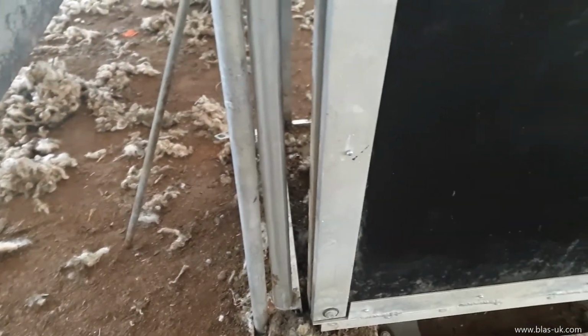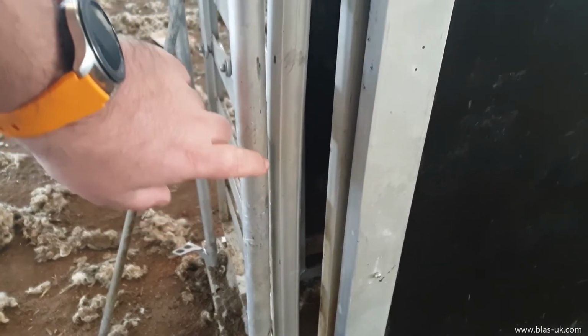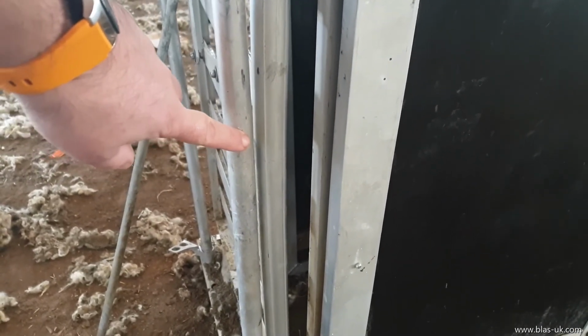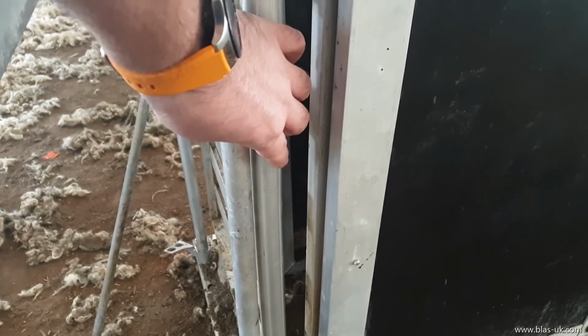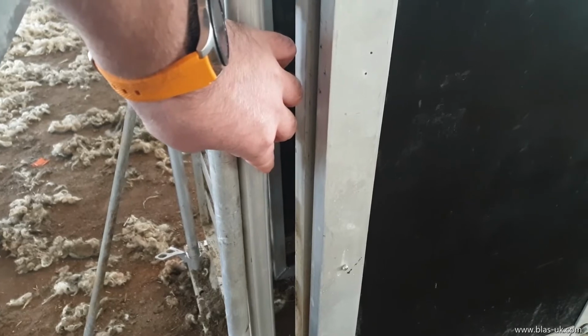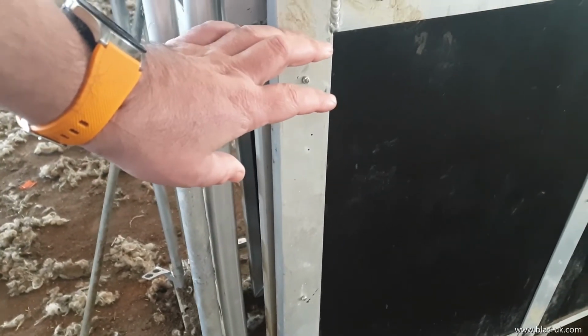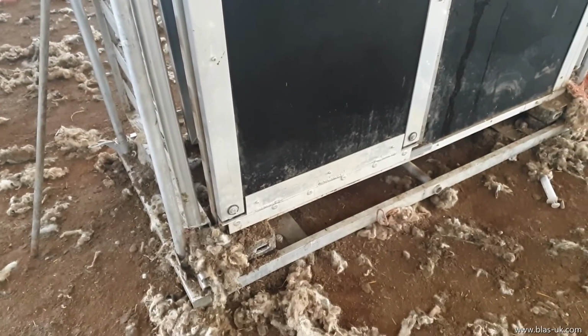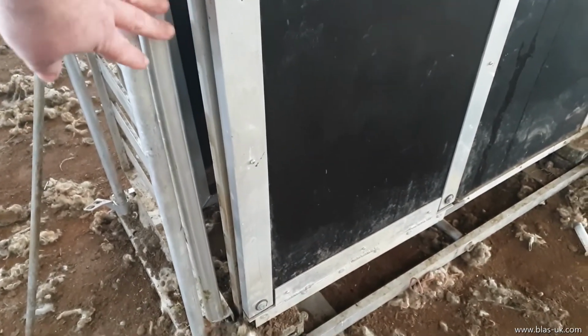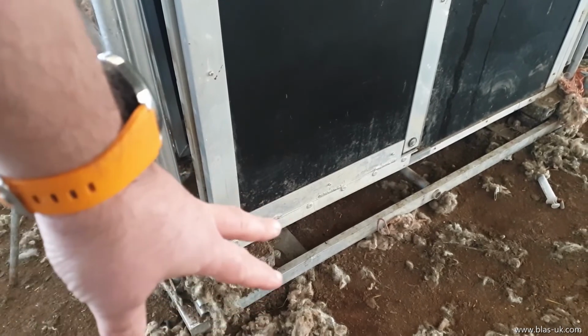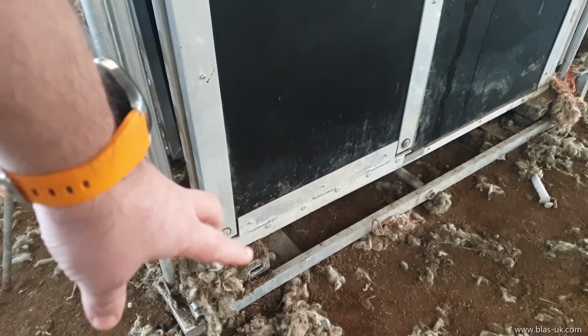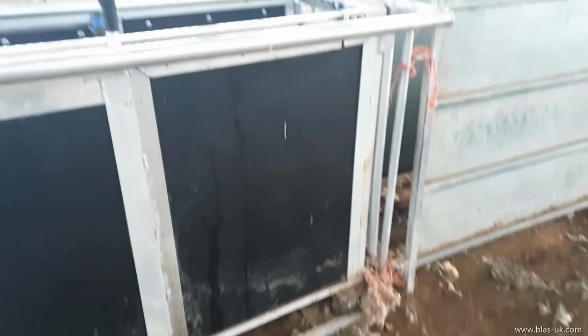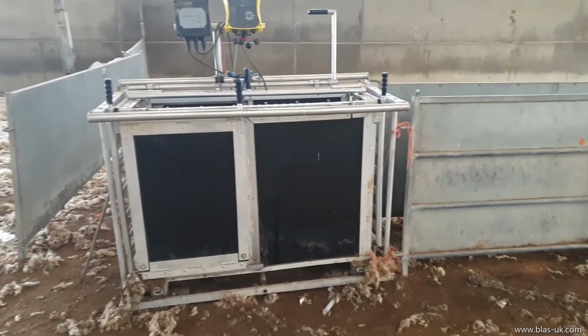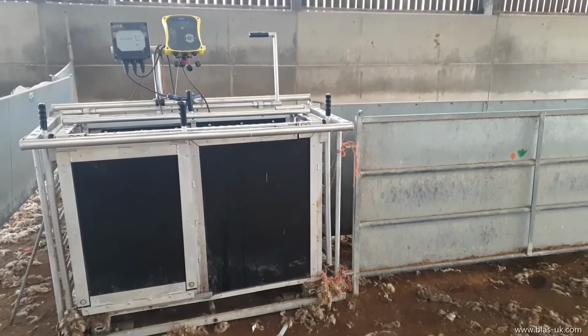Also, bends in gates between the gate and the isolation frame. Again, if these are slightly touching, this will then give you a resistance point, which will limit the ability for the weigh crate to push down properly on the load cell. Combining all three problems, the touching gate, the wool and stuff between the isolation frame and the load cell, then an unlevel weigh crate, we've got a combination of three things limiting our ability to give an accurate weight.